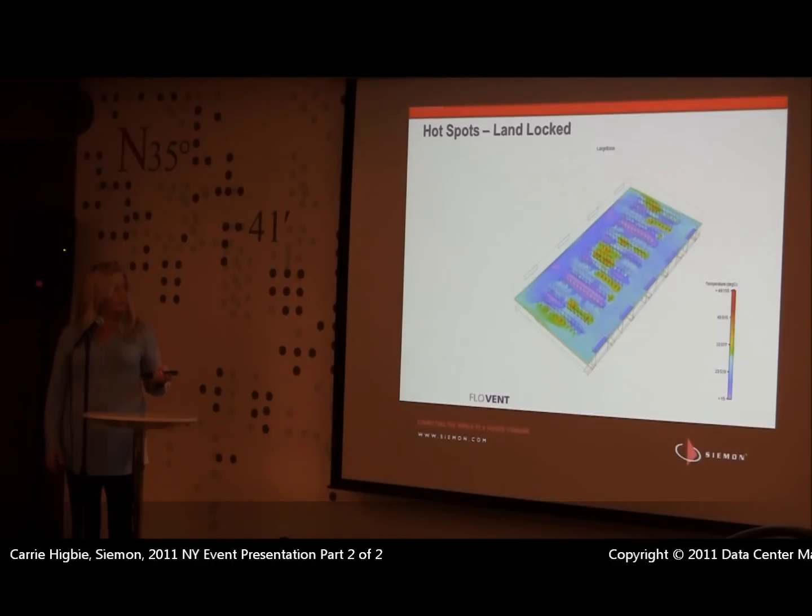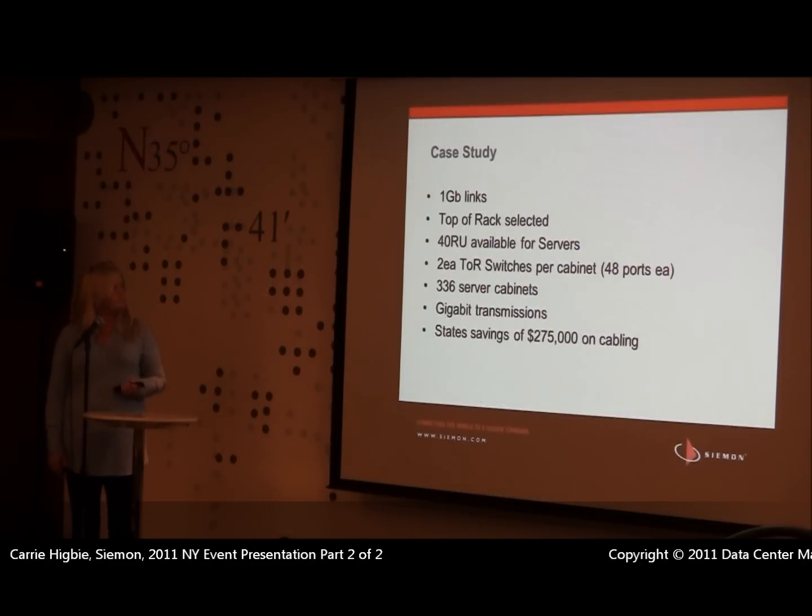If I buy a bunch of blade servers and the only place I have open network ports is in that spot, that's probably not where I want to put them. In a lot of cases, you can save money on your facilities by staggering your hottest equipment around that area as opposed to putting them in one. If you know you don't have capacity, it makes sense to build a high density area and provide supplemental cooling to that area instead of trying to beef up cooling in the whole data center.